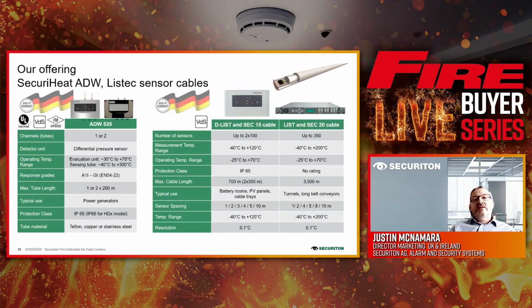And then on the right-hand side, our two choices for more typical linear heat cable, either the D-list or the list. Essentially, this is cable. We can provide resettable linear heat. If I look at the list cable, we can run a length of up to 3.5 kilometers, which is going to cover a very large, long area. And one of the key things I like about this, aside from being addressable linear heat, is the resolution. The fact that we can go down to 0.1 degrees Celsius really helps as far as temperature monitoring is concerned.